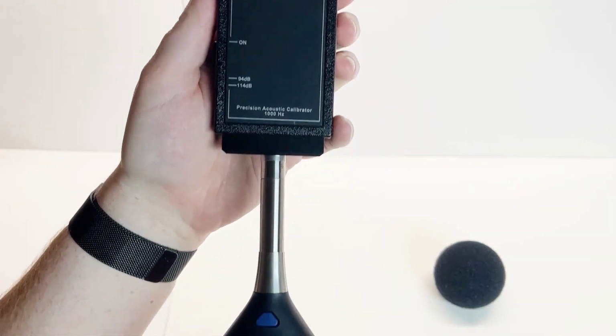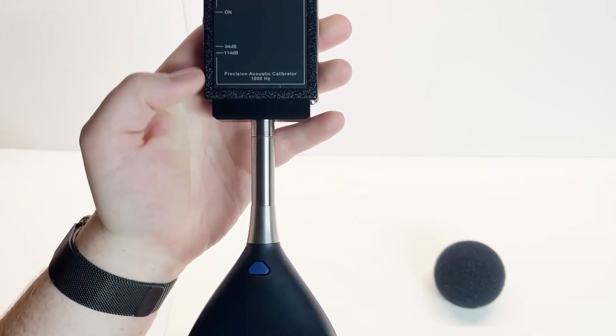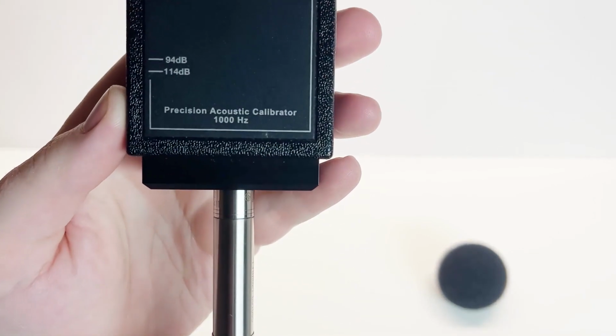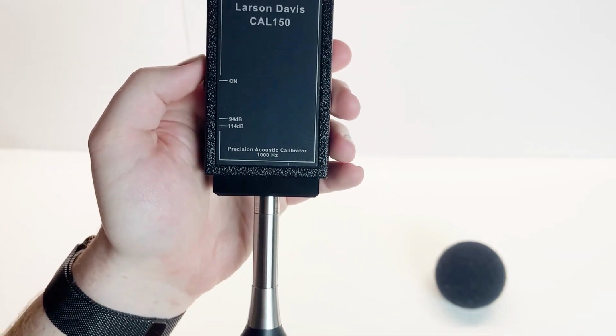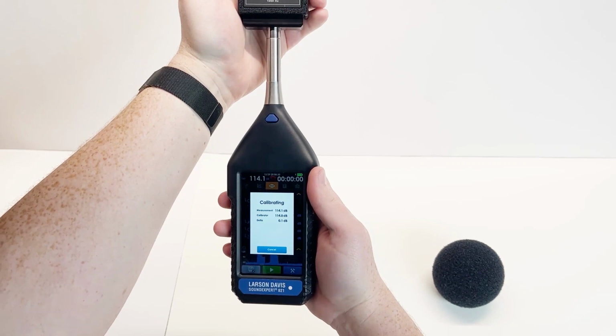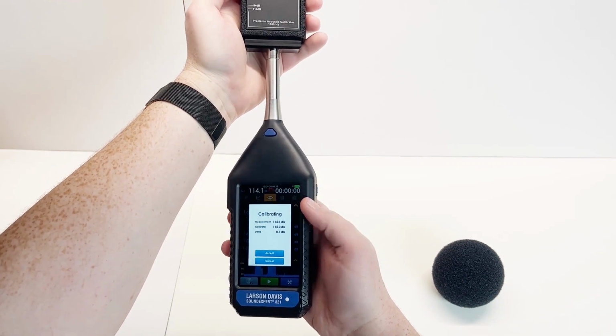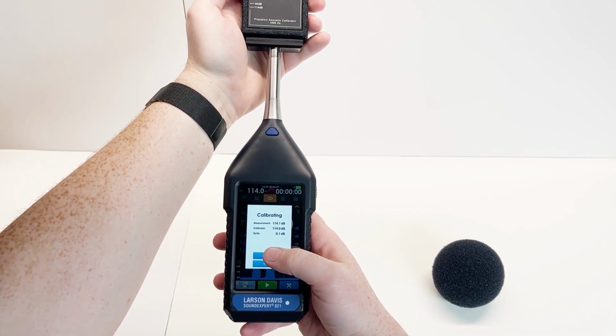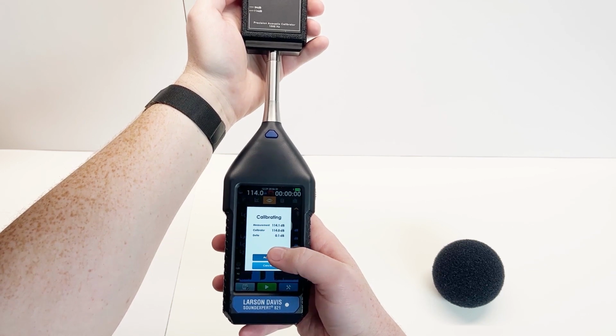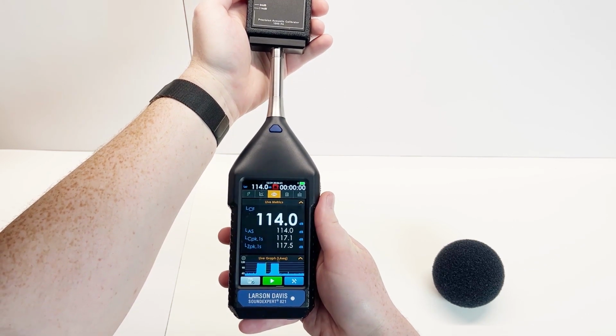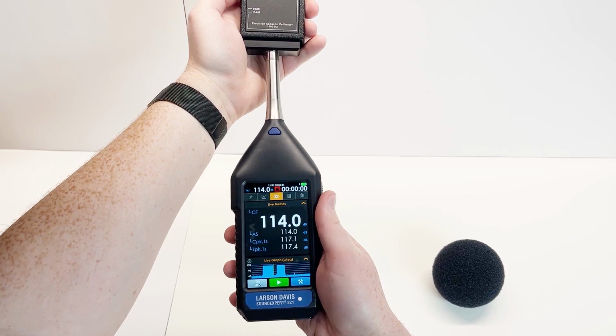And you can check this visually by looking at the bottom of the grid cap, and this will be flush with the bottom of the calibrator itself. The meter displays the calibrating dialog, which shows the measurement level, the calibrator level, and the detected change. Tap accept when the calibration is complete to accept the sensitivity.